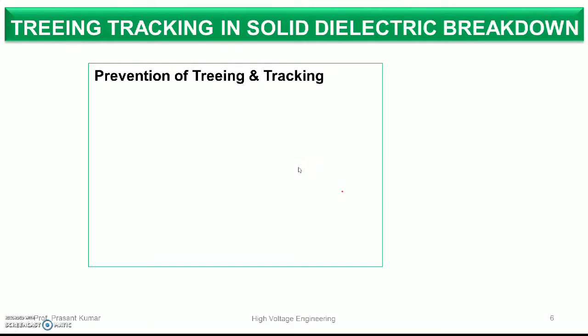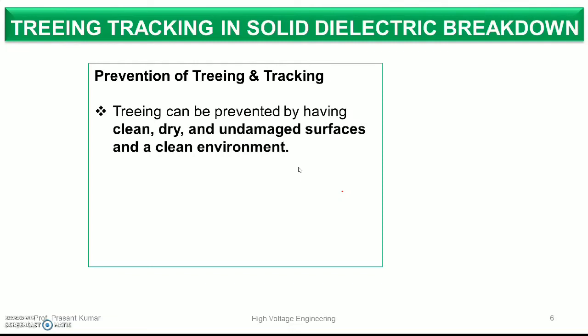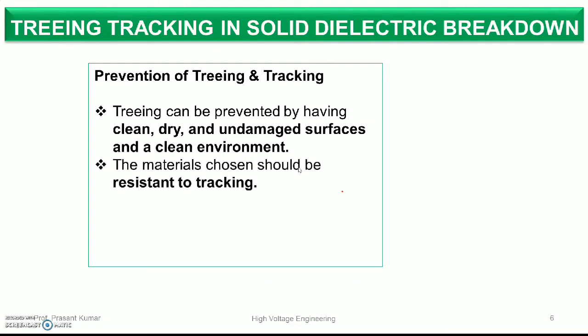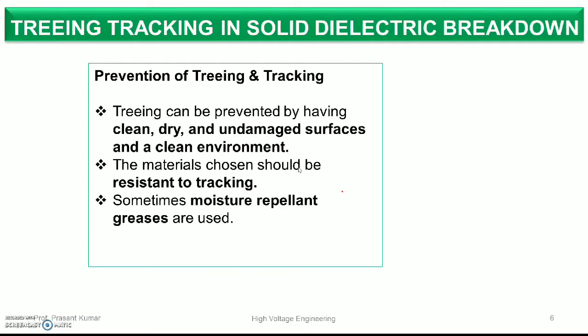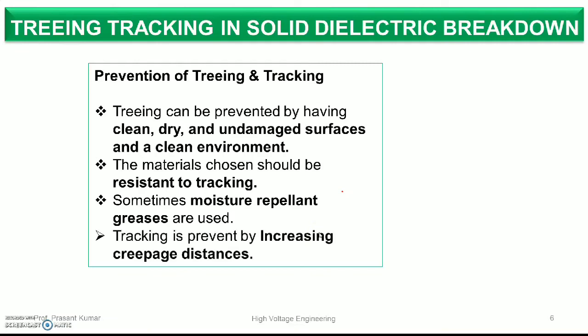Now, how can we protect against treeing and tracking in solid dielectric materials? Generally we do some practices: we keep the surface clean and dry, and minimize environmental impact on the surface. When choosing a material, we check its resistance and dielectric strength — it should be very high. We choose materials that are moisture-resistant, gas-resistant, grease-resistant, and oil-resistant. We can also increase the creepage distance between conductors and between two electrodes to minimize the impact of treeing and tracking.